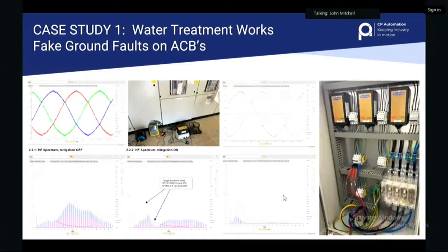If you look on the left-hand side here, this was the switching noise of the drives that was affecting the sensors. We installed 3 Sine Tamers - we had to fit 3 because of how far away we had to mitigate the problem. The people who owned the compressor, the OEM, said the warranty would be invalid if we installed a Sine Tamer in the cabinet. Even though 1 Sine Tamer would have solved the whole problem, because we couldn't put it at the source and we were 100 meters away, we had to fit 3 to mitigate that.